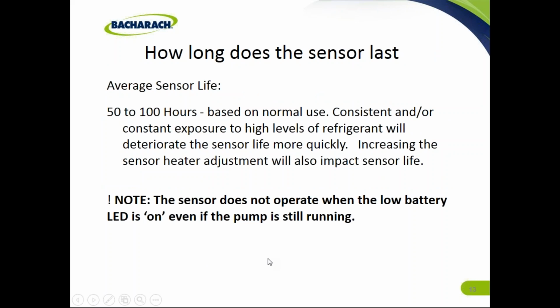Average sensor life is 50 to 100 hours based on normal use. Consistent and/or constant exposure to high levels of refrigerant will deteriorate the sensor life more quickly. Increasing the sensor heater adjustment will also impact sensor life. Note, the sensor does not operate when the low battery LED is on, even if the pump is still running. So when that low battery LED comes on and it's red, even though you hear the pump running, that sensor is not working. At that point, you have to go to a wall charger and charge it, or if you have the unit on, you can plug it in and continue to do your leak detection.